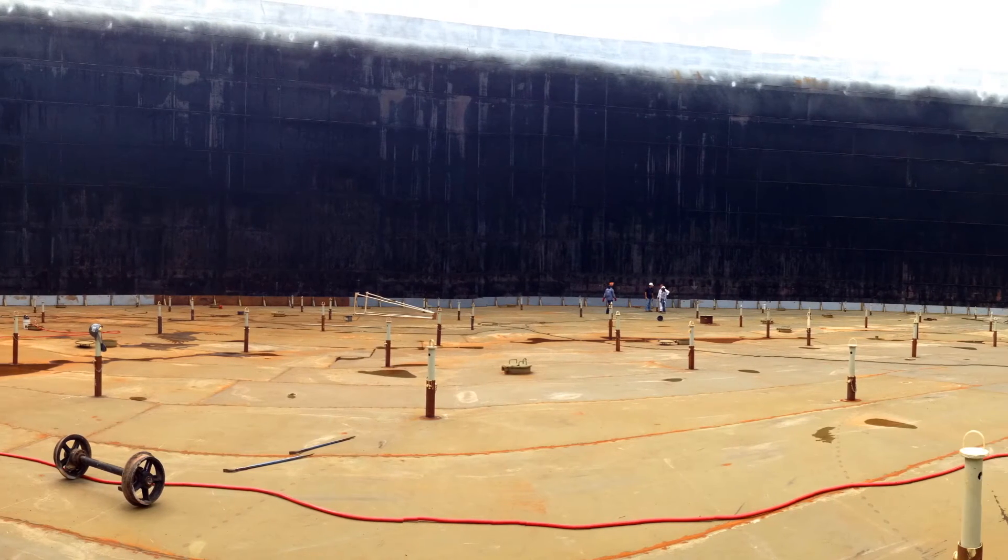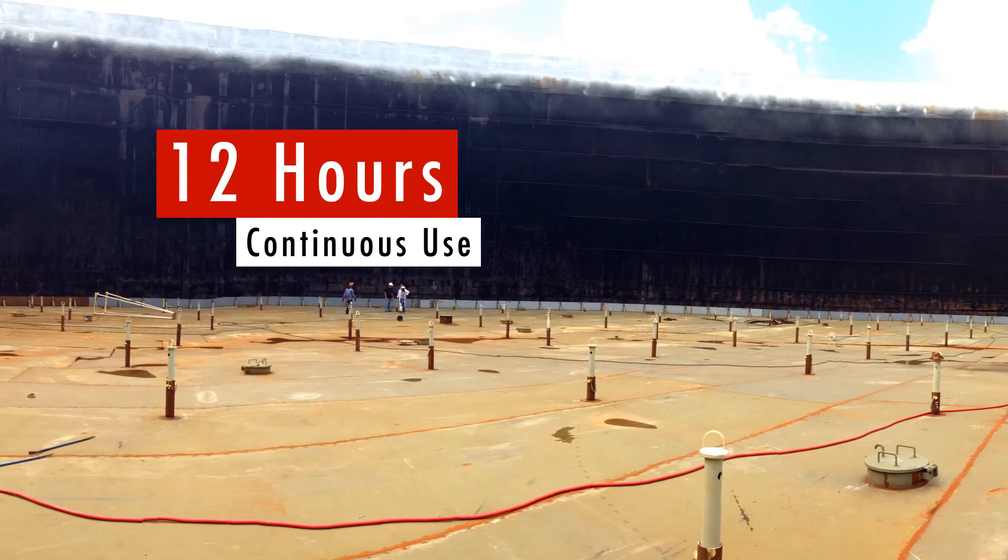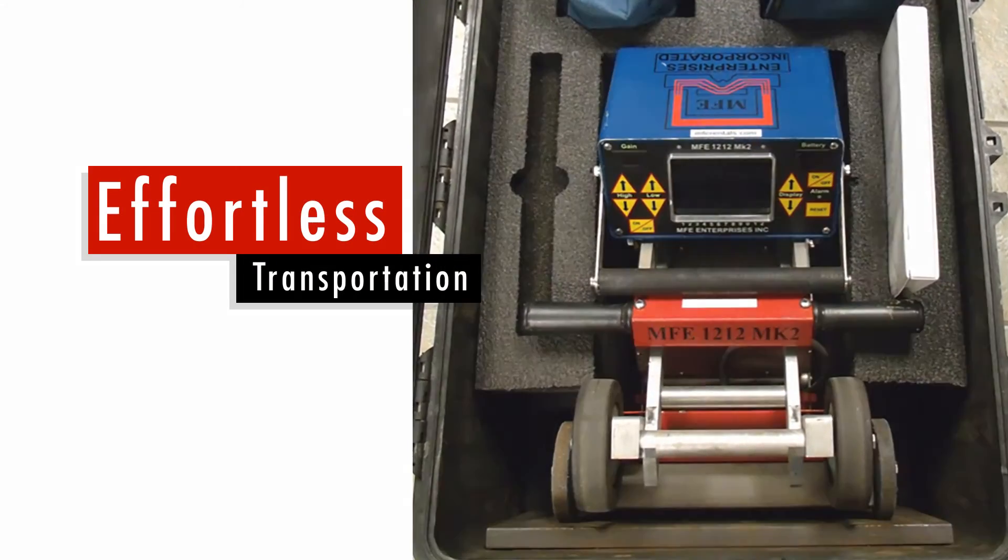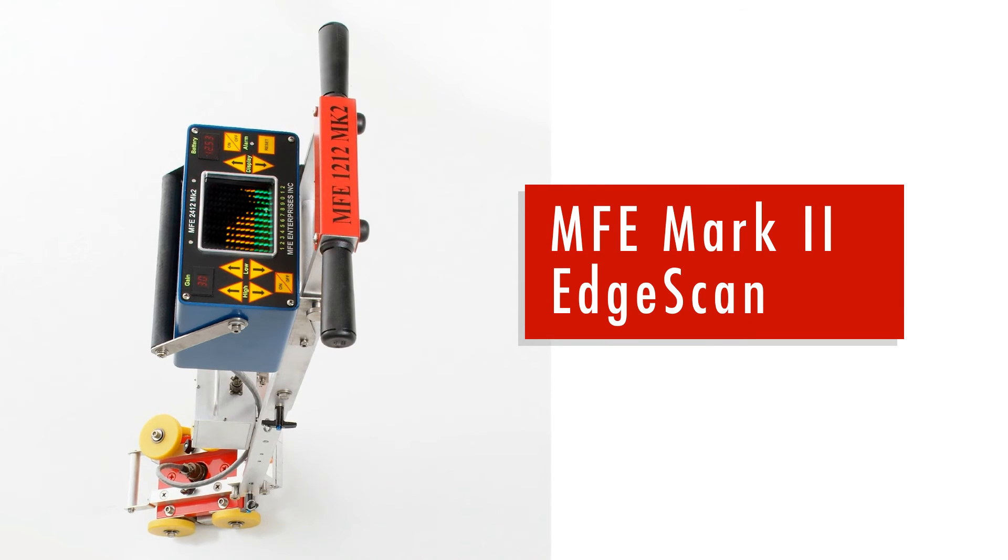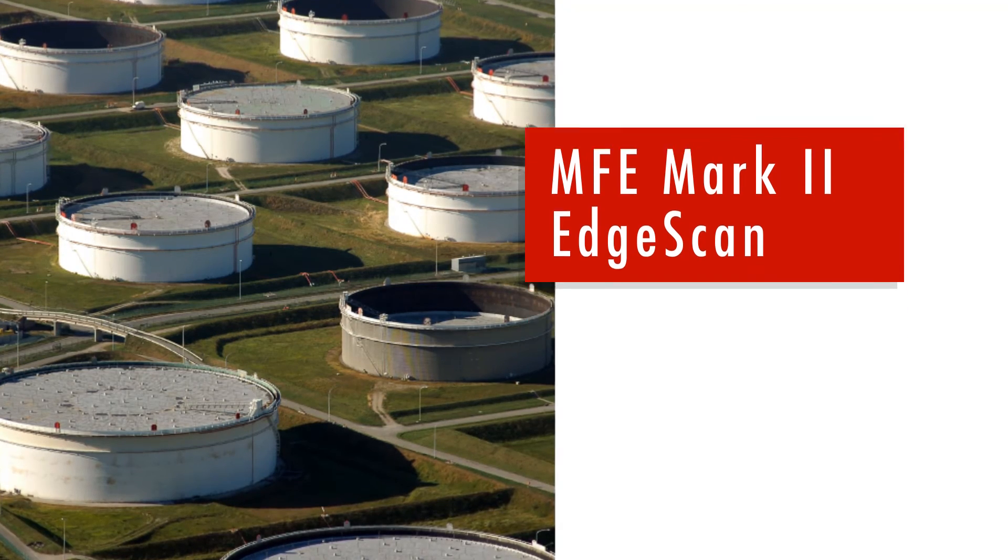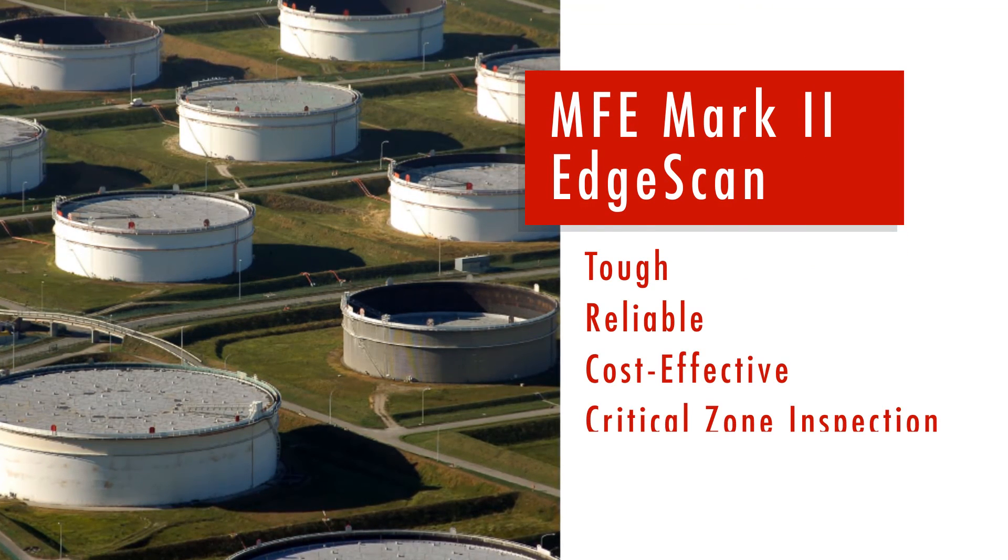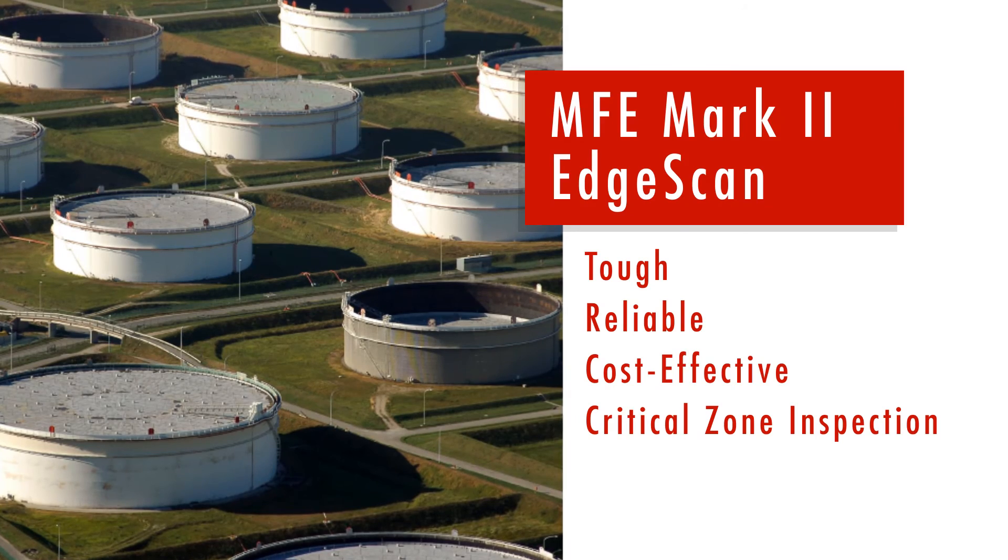It is also battery powered for over 12 hours of continuous use and folds down for effortless transportation. The MFE 1212 Mark II edge scan is a valuable tool for your next MFL tank floor inspection. It is tough, reliable and cost effective, and its value for critical zone inspection is undeniable.